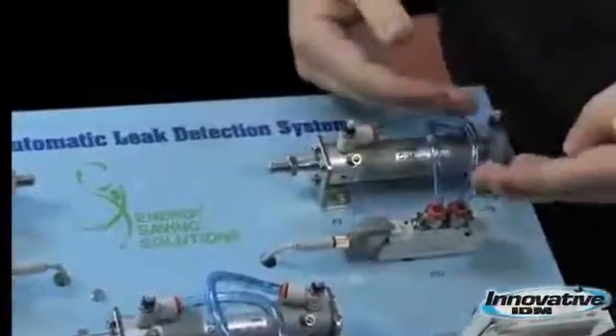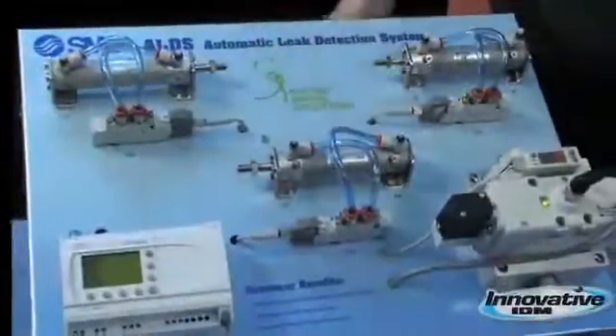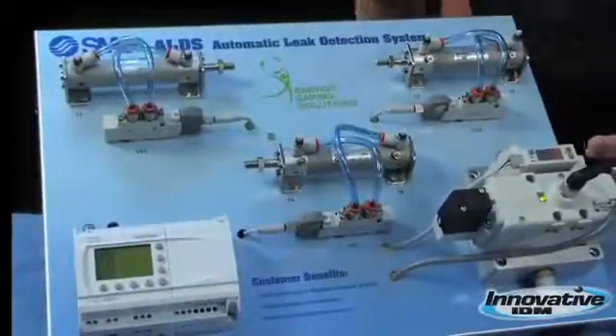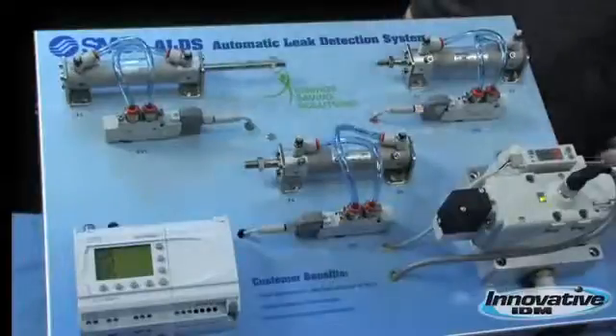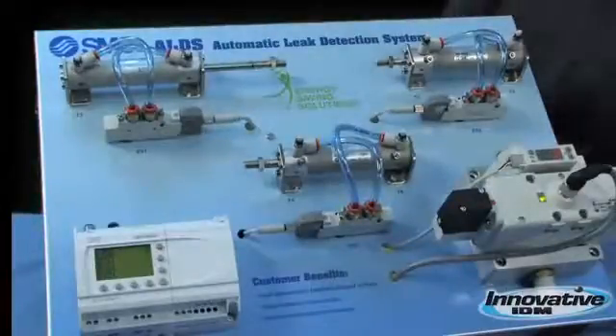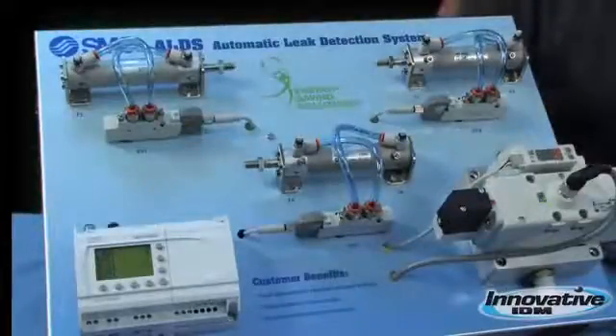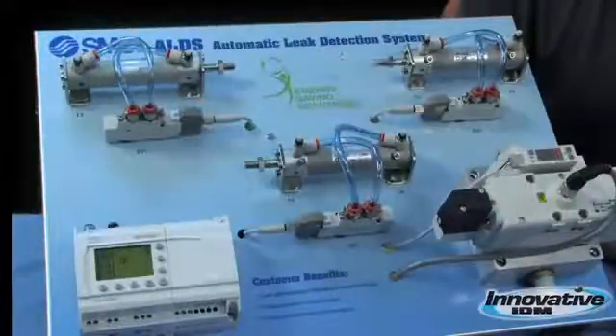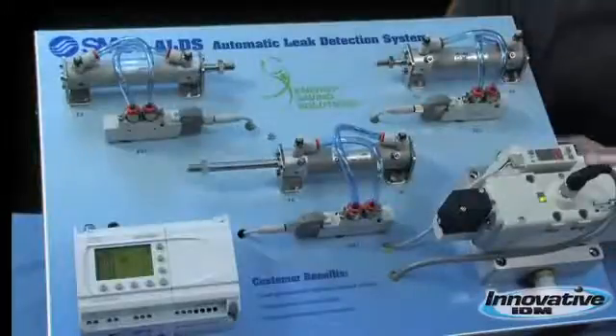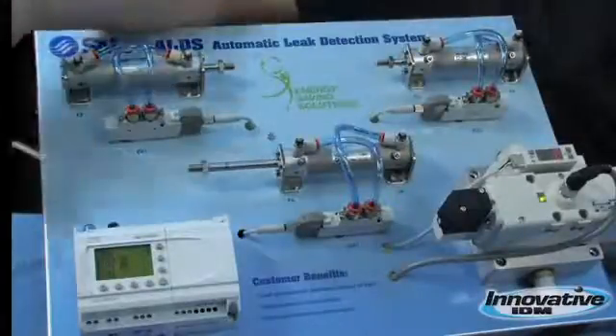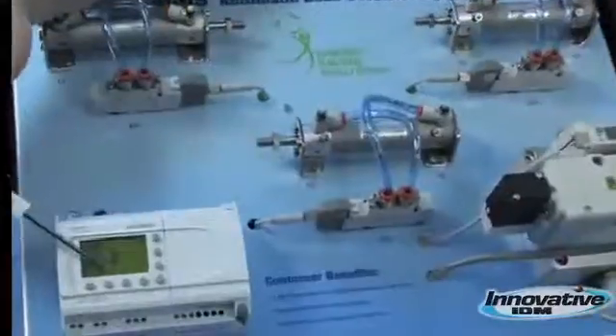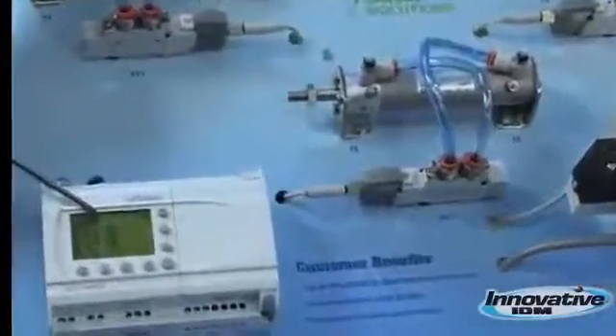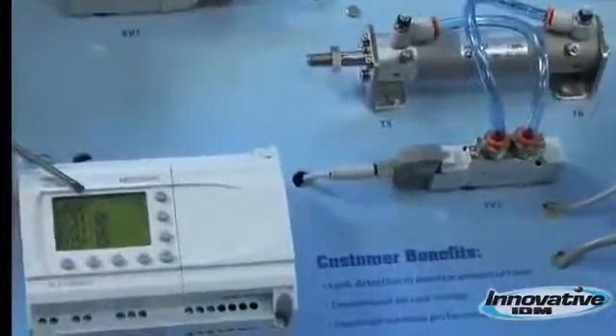And to verify that our fix took place, we can recycle the ALDS one more time. And as we can see, they've all gone back based off of the baseline. So we fixed the leak.